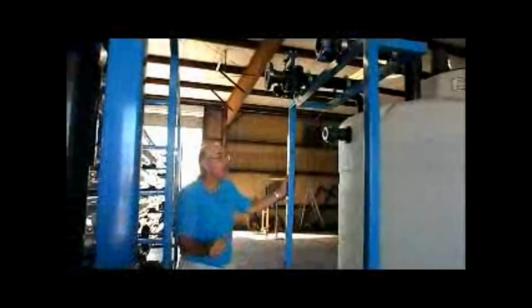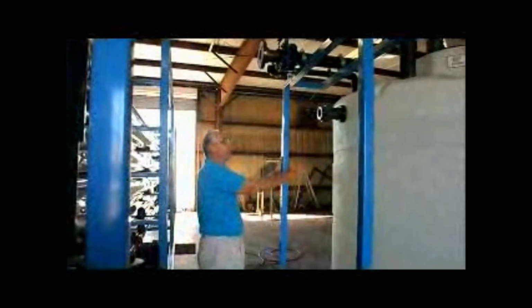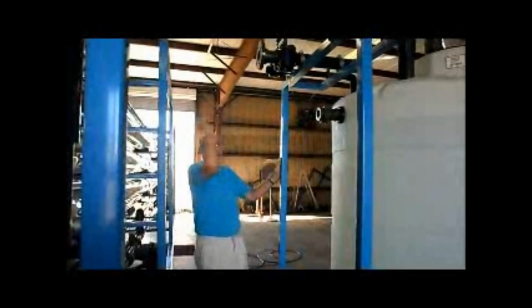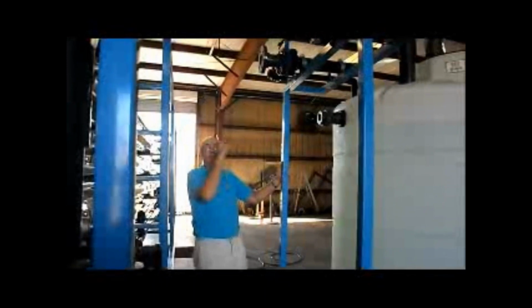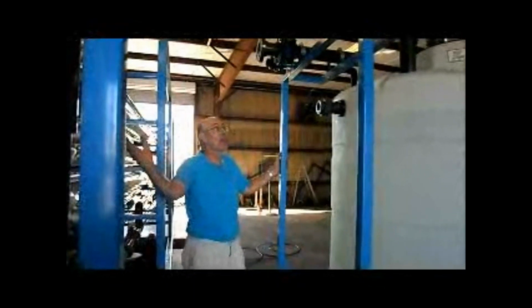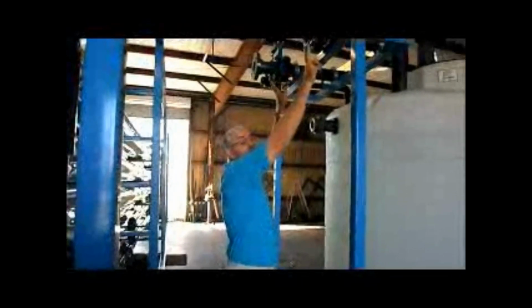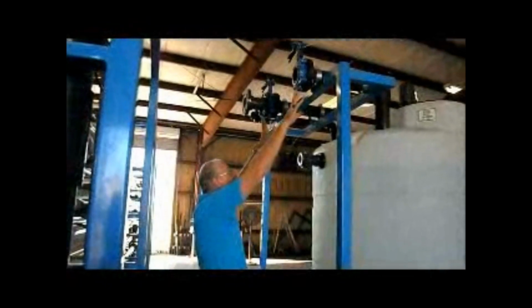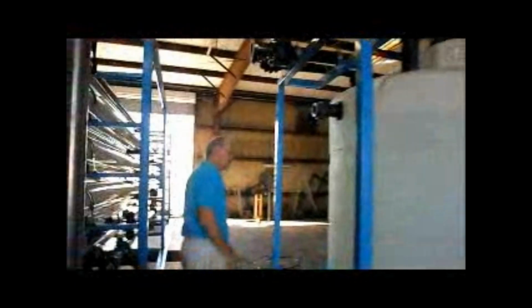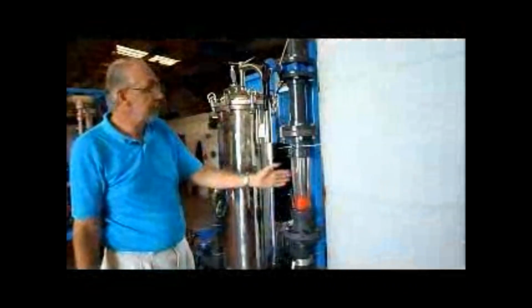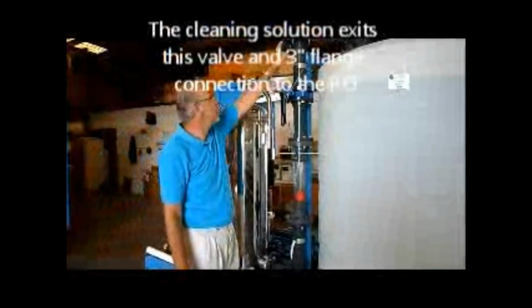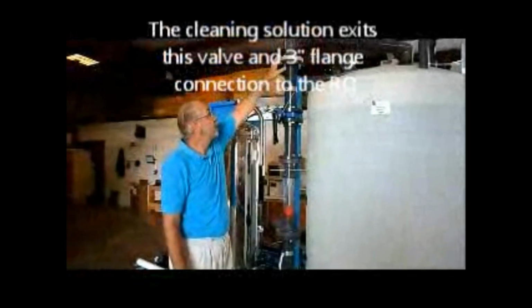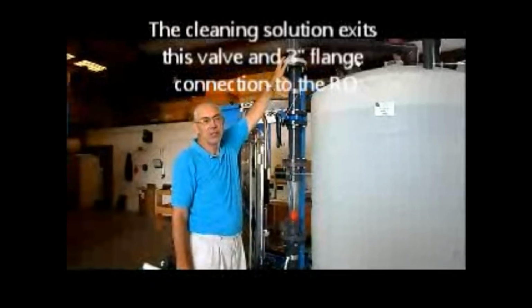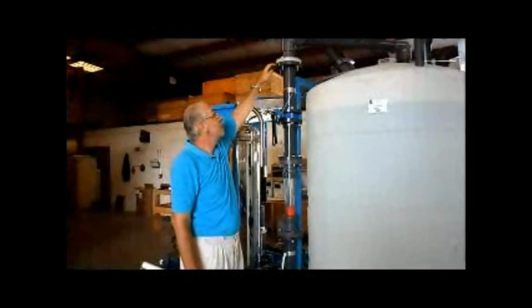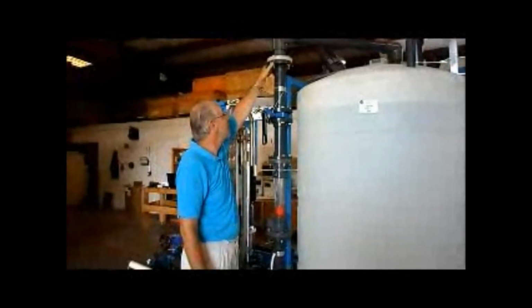So the way the cleaning station will work is the cleaning solution will be pumped out to the RO skid or out to the EDI skid, go through the EDI or RO skid, and then come back with these 2 pipes. Permeate, concentrate. Now on this side, you'll see the outlet. This is where the cleaning solution exits the system, through this valve and out through this flange.